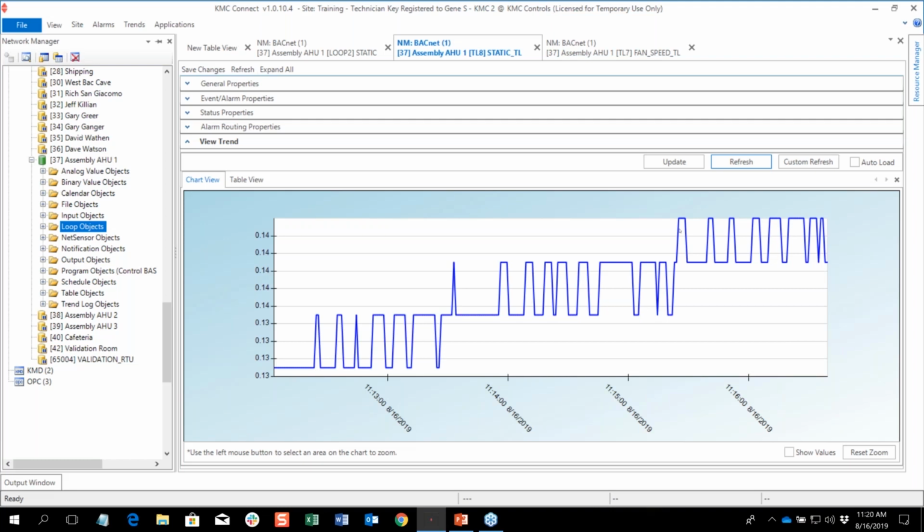Okay. Well, since we're not getting any more questions, the one last thing I would leave you with is that maybe this is a little bit of a surprise, but all of the Conquest controllers do have auto tuning built in. I would caution people, we still need to use good rules of PID loops if we're going to enable auto tuning to know what it's going to do. It follows a very similar process that Gene went through to tune this loop. It's going to start with a reasonable proportional term, and it's going to slowly adjust that to try to eliminate ringing.